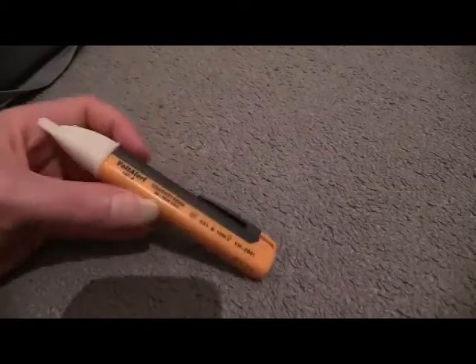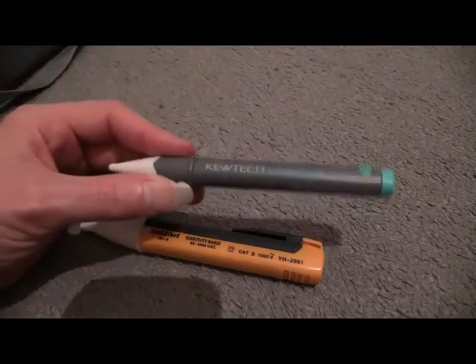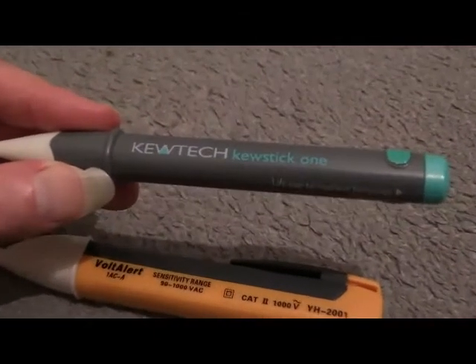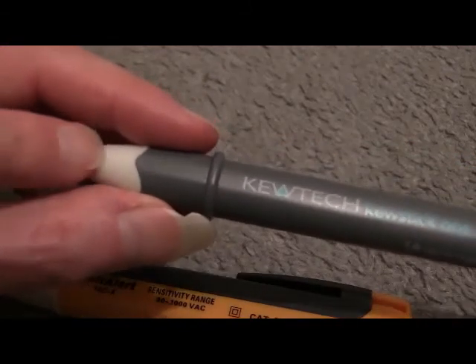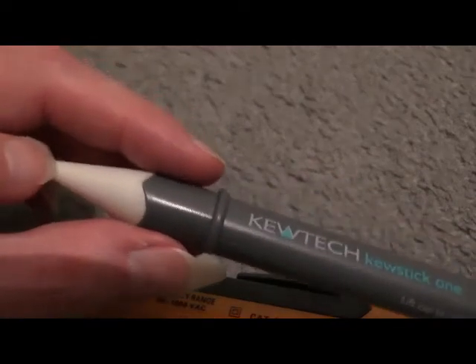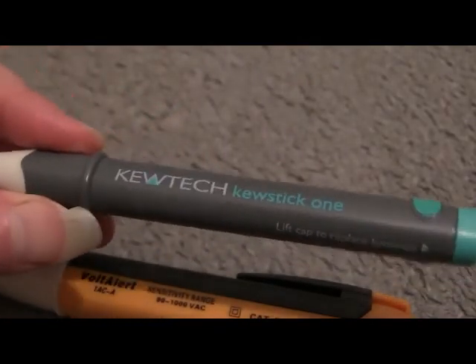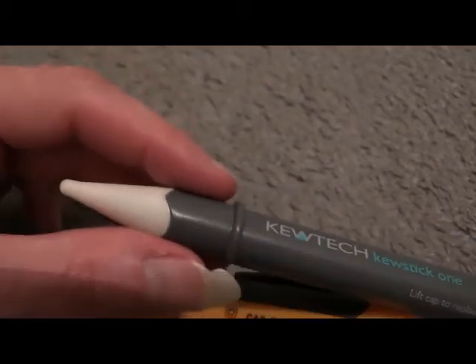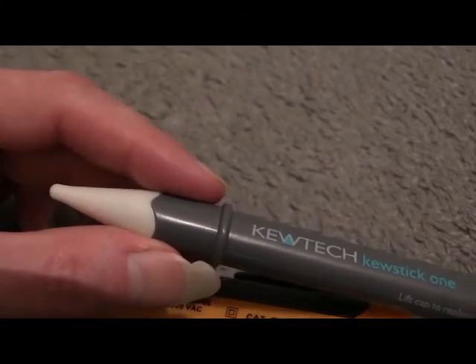So that's volt stick number one. What about the other one? Well, this one they claim is made by Kewtech — it's a Kewstick One. Rather like the other one, you've got the tip at the end: when you get it near a live power cable or wiring accessory, it illuminates red. I did actually have an issue with this some time back — I had batteries in it, opened up the case of test equipment just to get one of my testers out, and this thing was just glowing inside the case. I couldn't turn it off, I couldn't do anything with it. There isn't a switch on it — you can't turn it on or off.